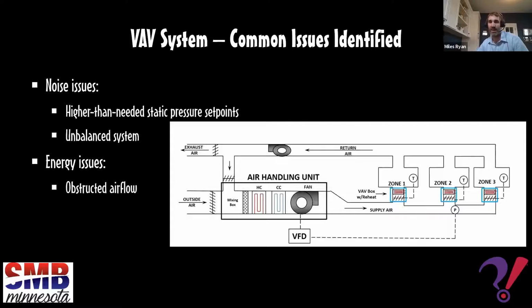So once the TAB contractors, or the TAB firm, came in there, and they have eyes into the system that a lot of the other people on the construction team just don't have, right? They were able to identify there's some sort of obstruction going on there. They looked further, they found this insulation had failed, and they got that addressed. But up until that point, there were some energy issues, right? That fan was working harder than it needed to meet the airflow requirements of the space.